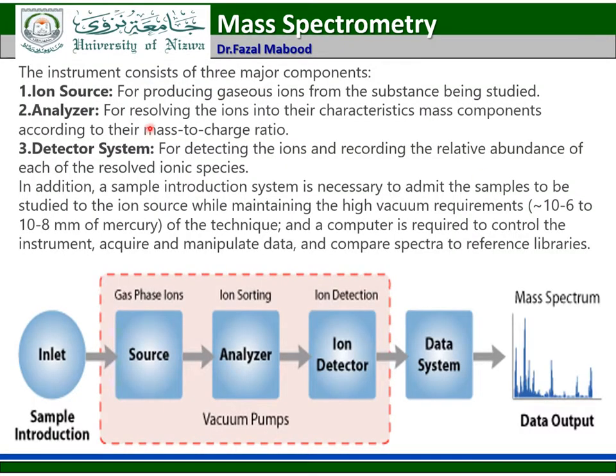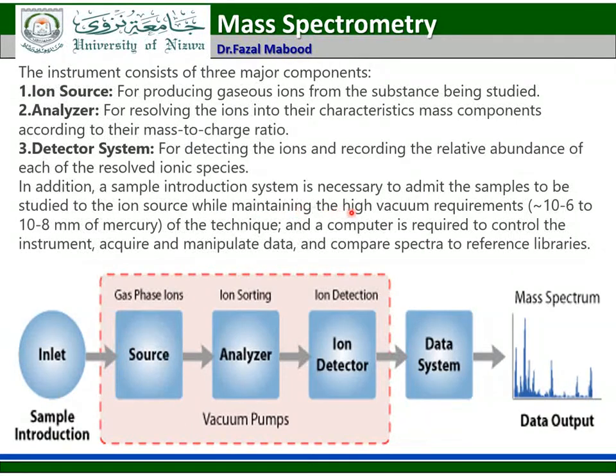A mass spectrometer consists of three major components: ion source, analyzer, and detector system. The ion source produces gaseous ions from the substance being studied. The analyzer resolves the ions into characteristic mass components according to their mass-to-charge ratio. The detector system detects the ions and records the relative abundance of each resolved ionic species. In addition, a sample introduction system is necessary to admit the sample to the ion source while maintaining the high vacuum requirement, and a computer is required to control the instrument, acquire and manipulate data, and compare spectra to reference libraries.